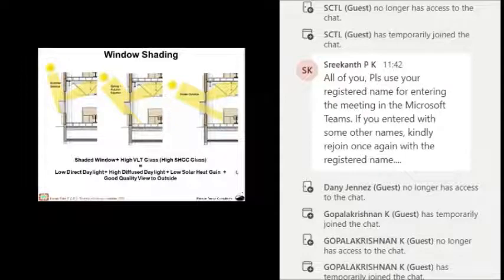For designing window shades, we all know about vertical shades and horizontal shades. If there are windows above the horizontal shades, then the horizontal shades can also act as light shelves, which help in better daylight penetration in the building, which helps in good quality daylight within the building. So we should design our buildings with windows which are properly shaded, with glass with relatively high VLT, so that the heat gain is minimal while quality daylight is there and our dependency on artificial light and air conditioning is minimal.